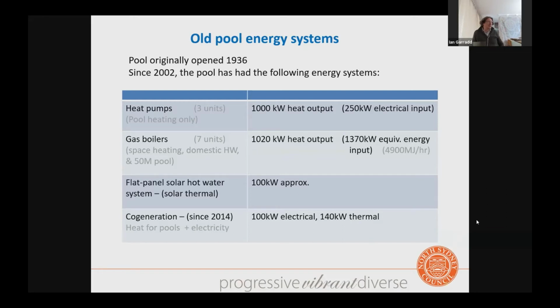The flat panel solar hot water system was around 100 kilowatts — documentation on it wasn't available, as we lost it many years ago, but we believe the output was around 100 kilowatts, a substantial amount of heat. It was generally used as a preheat for the pool, so it was very low cost heat and always utilised whenever heating was required.